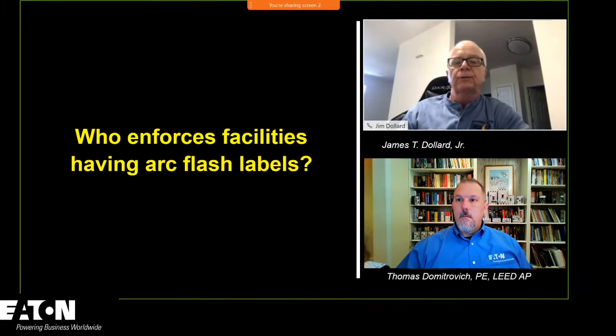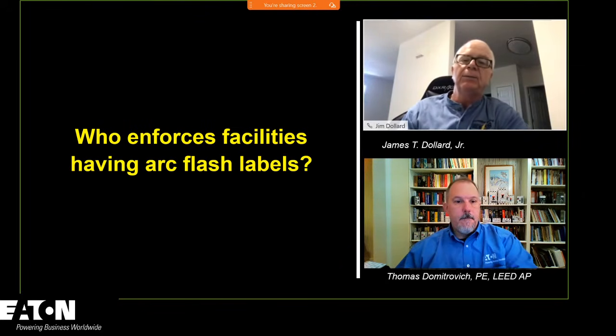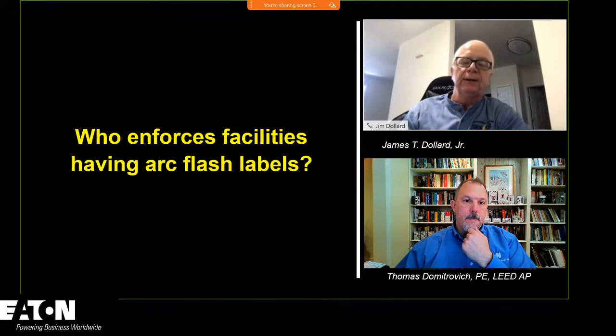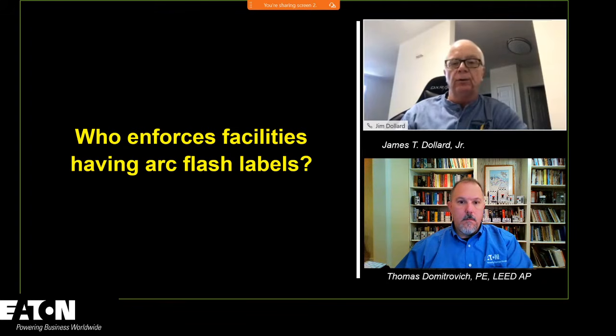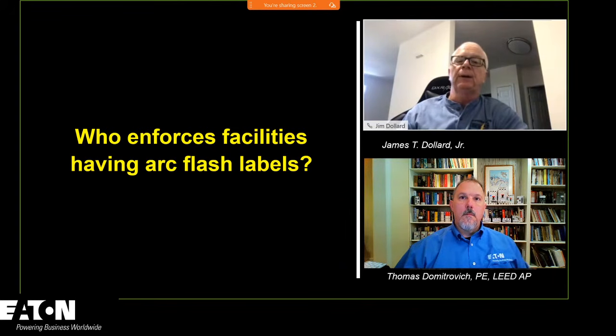But people often ask, who enforces 70E? Who enforces arc flash labels? There has been a lot of confusion around the labeling requirements in NFPA 70E. I've been involved in many scenarios where an engineer or owner, with a new building erected, doing the punch list, tells the electrical contractor, you've got to put the labels on, we want incident energy and the working distance. That is not a requirement in the National Electrical Code, which means it's not enforceable by the electrical inspector.